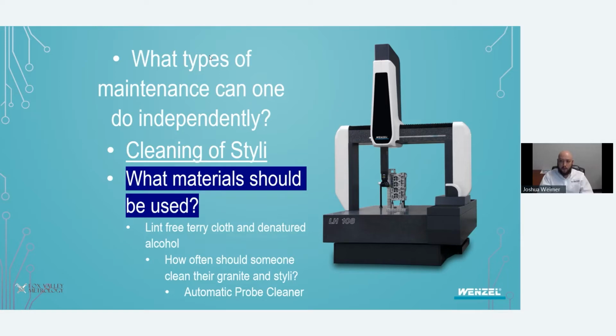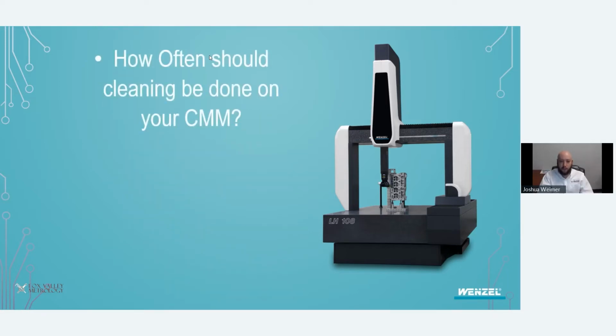Can you touch on how frequently the CMM cleaning should be done? It's going to depend on your situation. Key factors will be usage, environment, types of accuracies you're holding, and even the types of parts you're measuring. Some customers may need to do this more frequently than others. If you're experiencing excess dirt on the granite, residue or grease from your workpiece, or especially material wear or buildup on the tips which could lead to inaccurate measurements, you might need to do it more often. But a general rule of thumb is once a week is a great start.